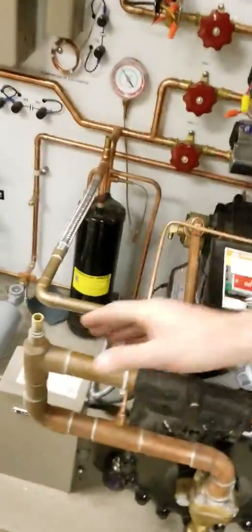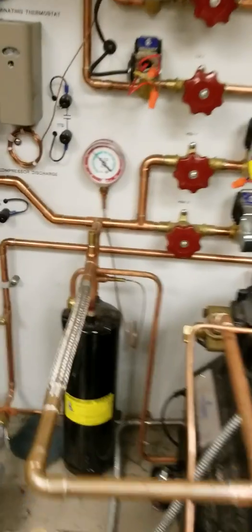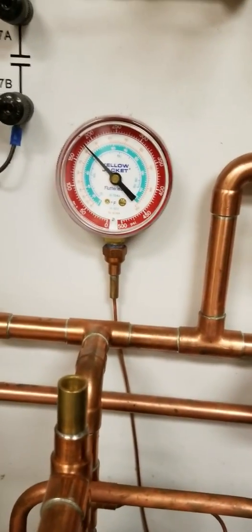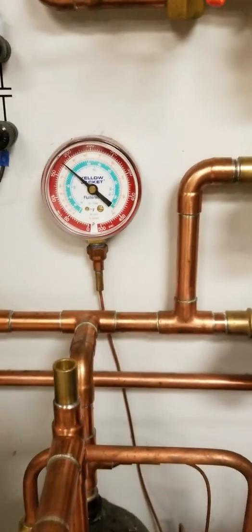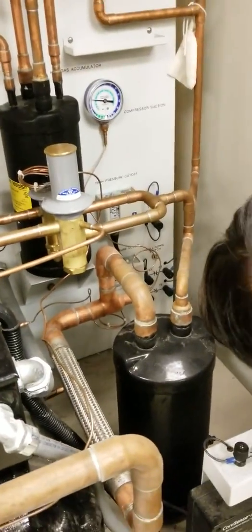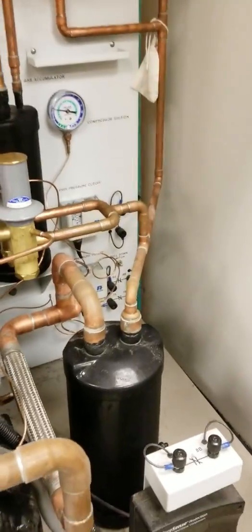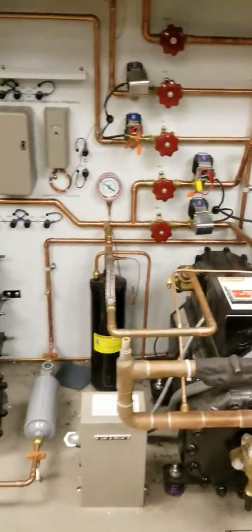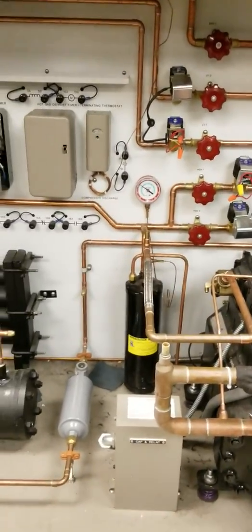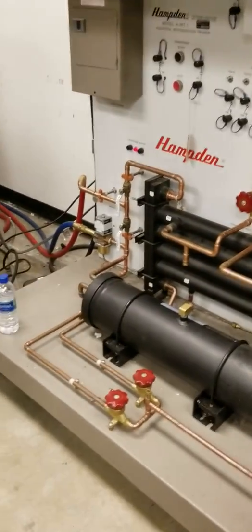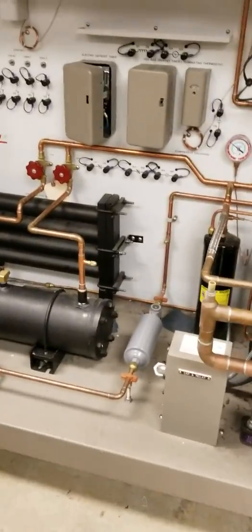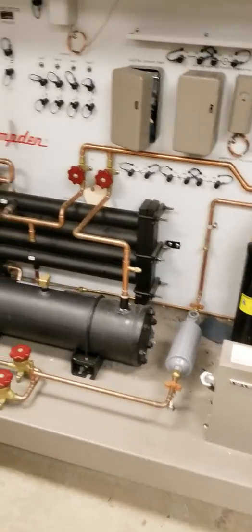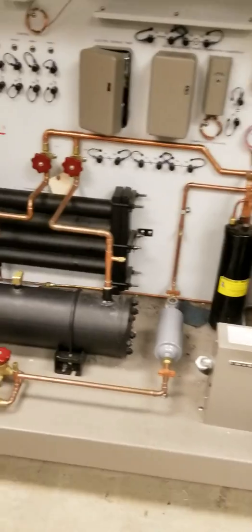Yeah. And you could watch our pressure as it starts to cool down from ambient. As soon as it goes below its 50 psi differential, it's going to cut back on. Oh yeah. Okay. It's a cut in, cut out. And it'll just keep going back and forth like that until the tower's turned on. Yeah, so why don't we turn the water on? Start circulating water. I can turn on the cooling tower.